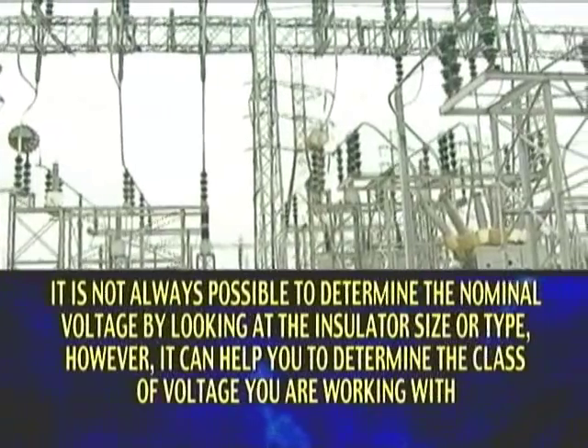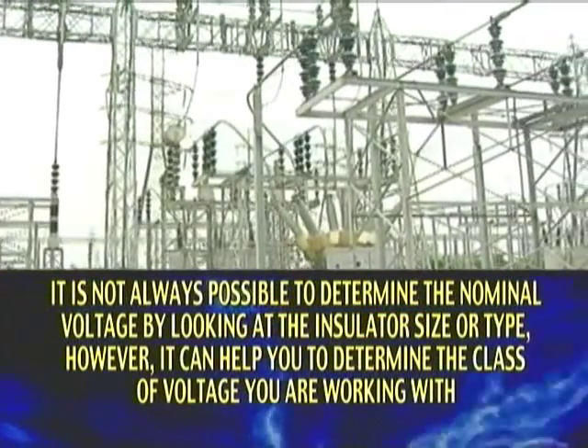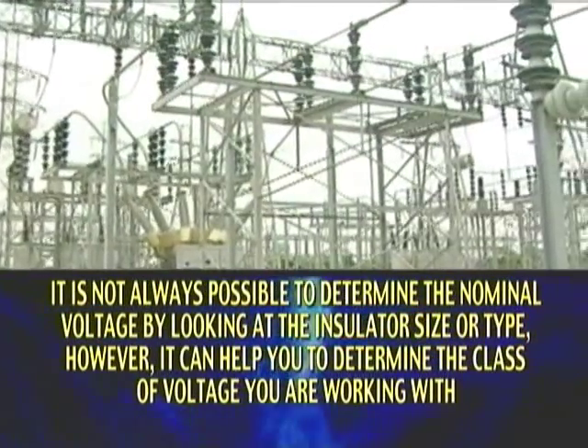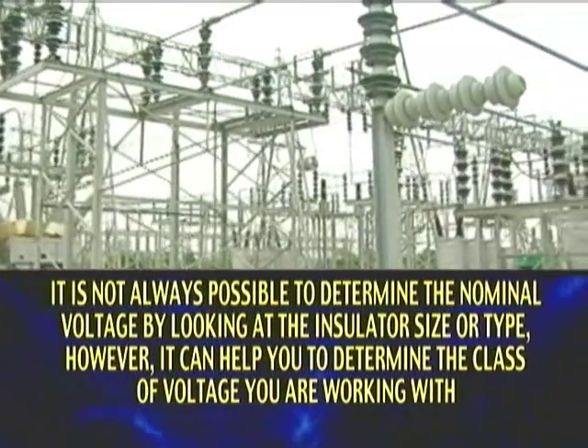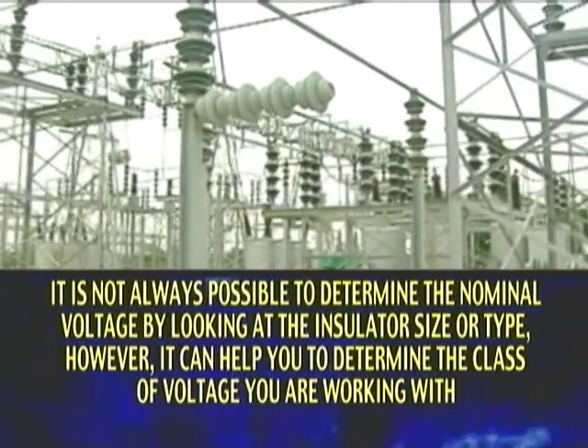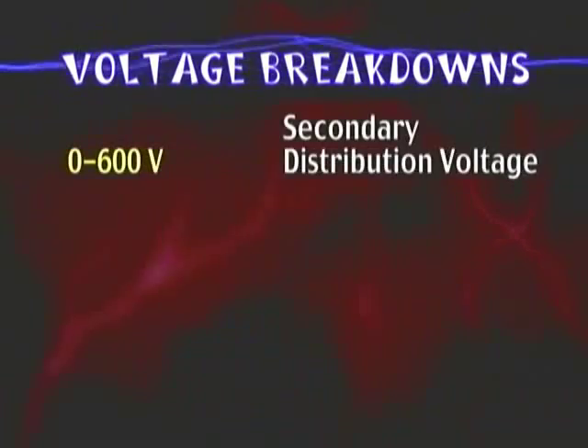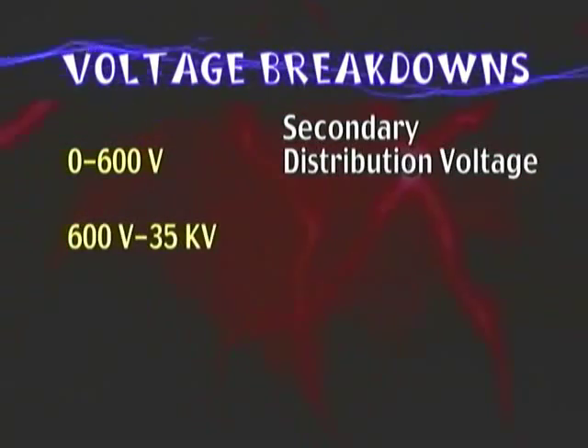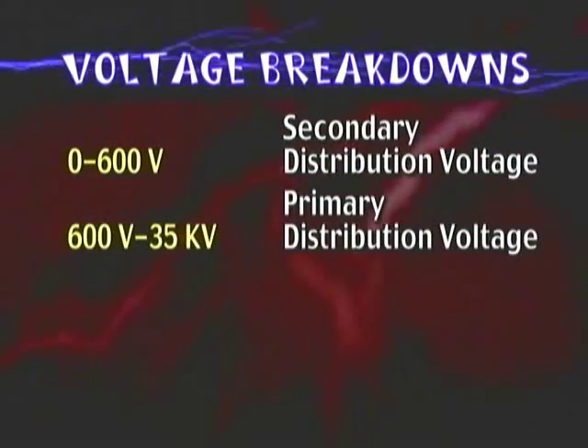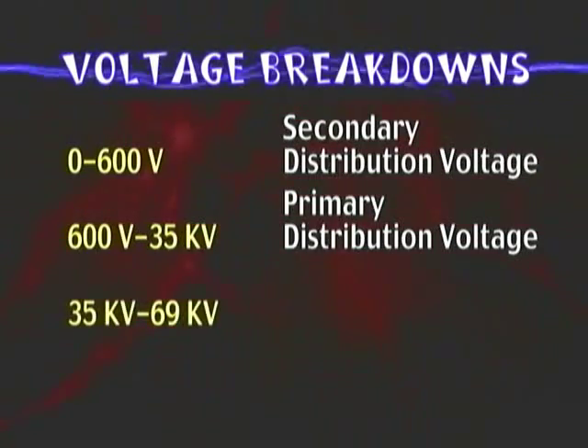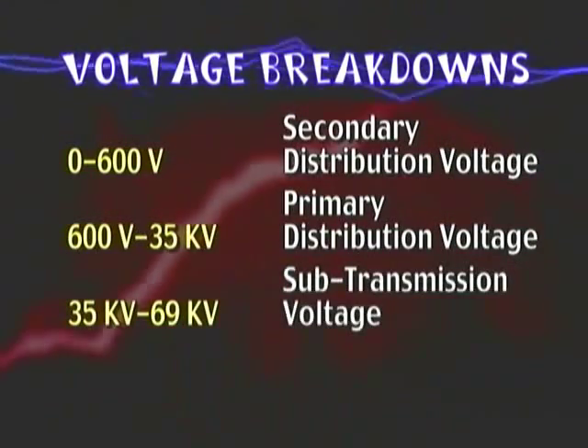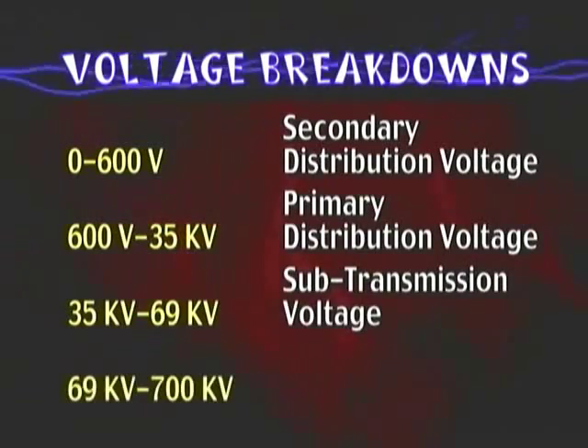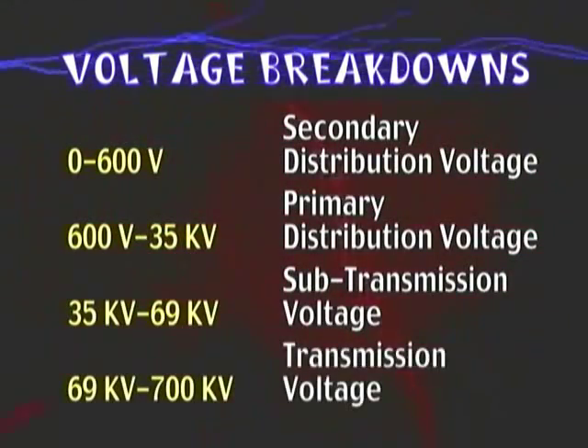It is not always possible to determine the nominal voltage by looking at the insulator size or type. However, it can help you to determine the class of voltage you are working around. Voltage breakdowns are 0 to 600 volts, secondary distribution voltage; 600 volts to 35 kilovolts, primary distribution voltage; 35 kilovolts to 69 kilovolts, sub-transmission voltage; and 69 kilovolts to 700 kilovolts, transmission voltage.